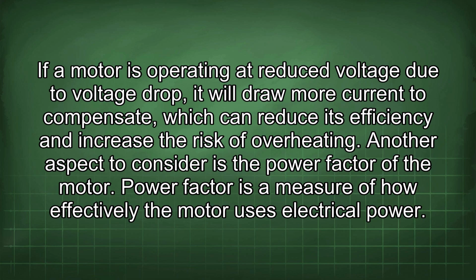If a motor is operating at reduced voltage due to voltage drop, it will draw more current to compensate, which can reduce its efficiency and increase the risk of overheating. Another aspect to consider is the power factor of the motor.